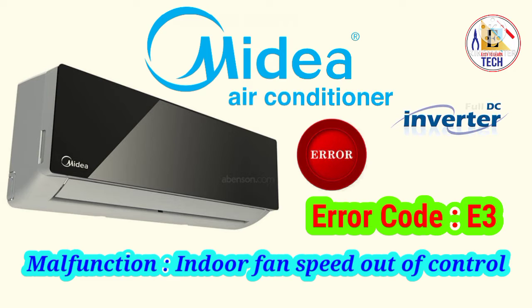Step by step you have to check the indoor PCB. If you are getting output supply properly from the indoor PCB, it means your indoor PCB is good. If you are not getting it properly, then you have to change your indoor PCB and you will get the solution for the error E3. Sometimes the output supply which is going to the fan motor, giving all the commands of the motor, if it is not properly given back to the PCB, at that time also we get this error. Then you have to change the fan motor and you will get the solution for the error E3.